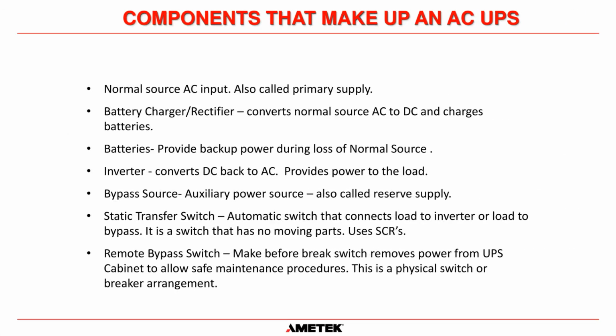But we do have to get rid of a few of the common terms that we use so you understand what we're talking about. So when we say normal source AC input, that is the grid power that goes into the UPS that supplies power to the charger section of the UPS. Okay, battery charger and rectifier, that's self-explanatory. That converts normal source AC to DC and charges the batteries. Also supplies power to the inverter.